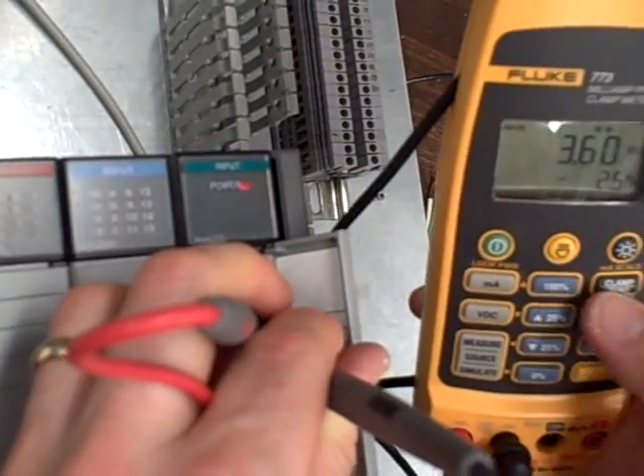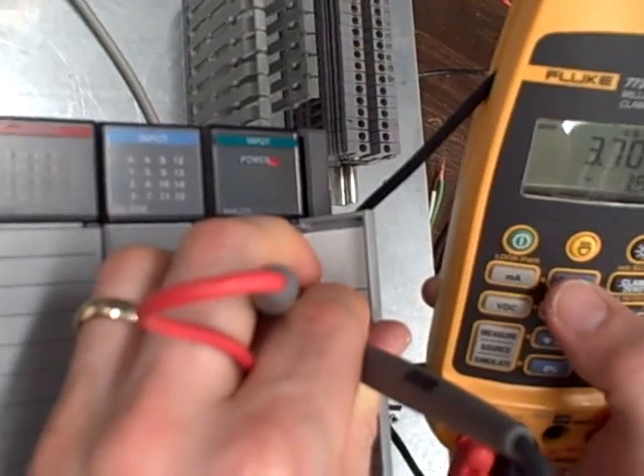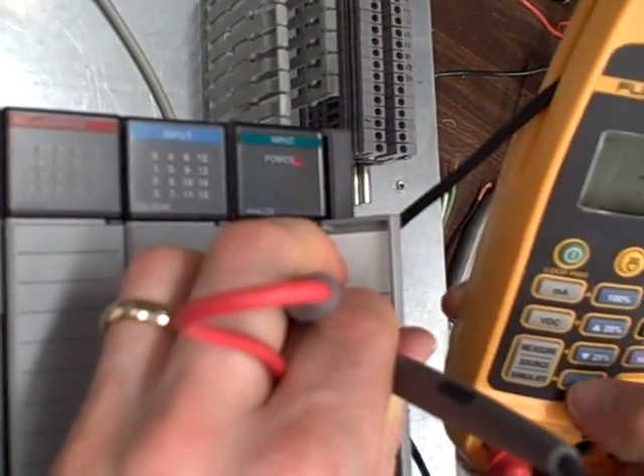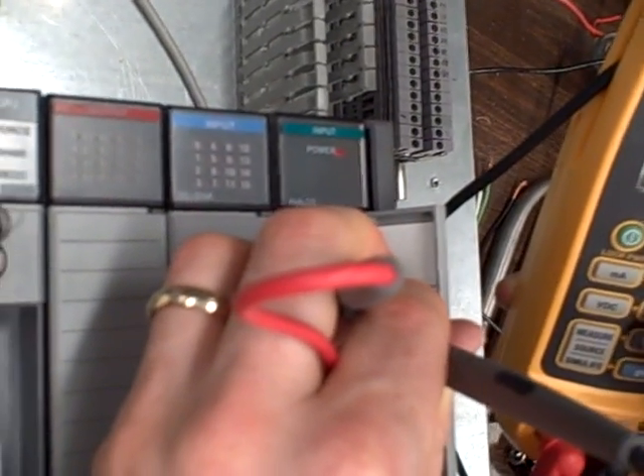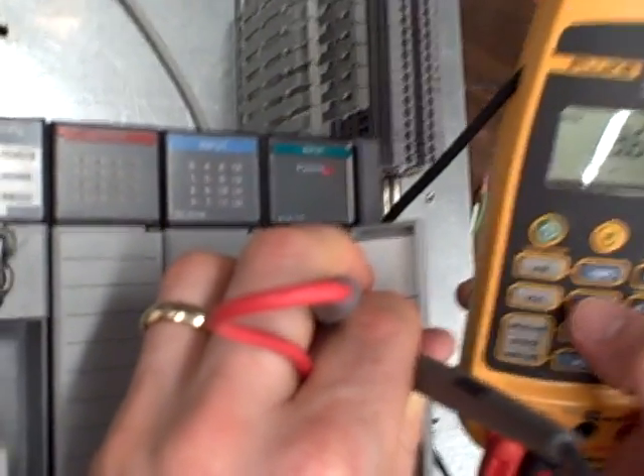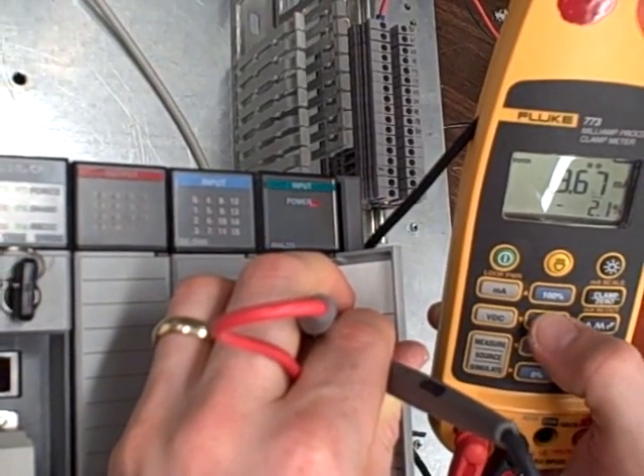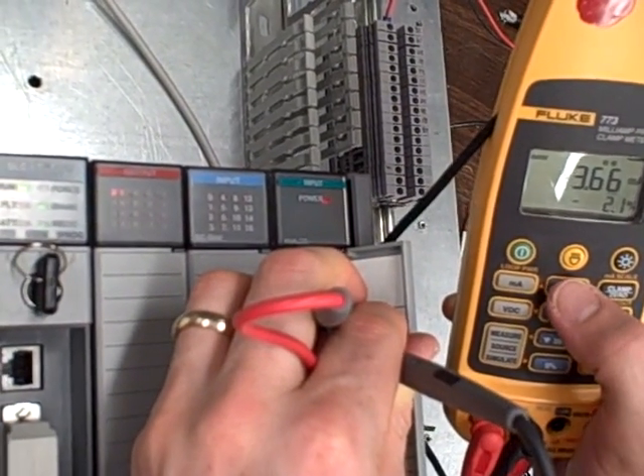Right there. 3.6 milliamps. I get that light. I go to 3.7 milliamps, light goes off. I can actually scroll over and find your steps. 3.69, 3.68, 3.67. Right there. 3.66.